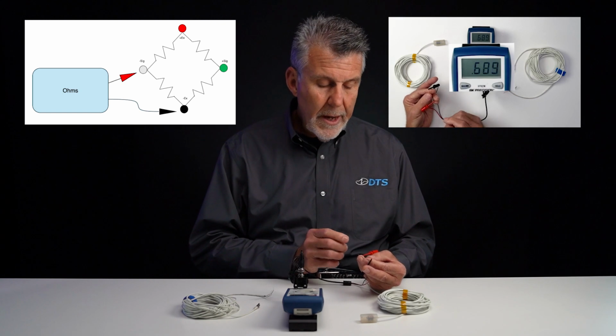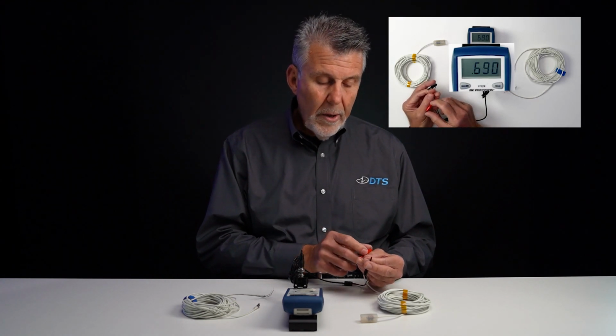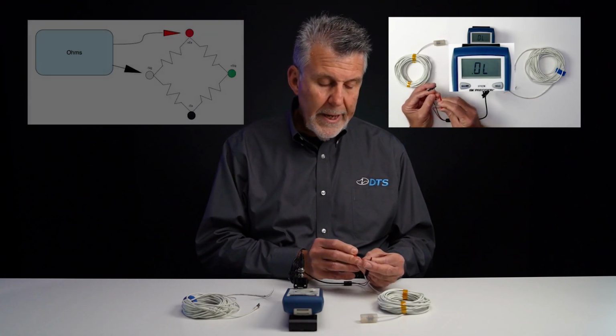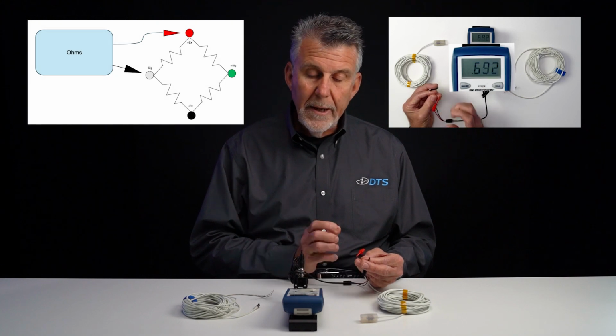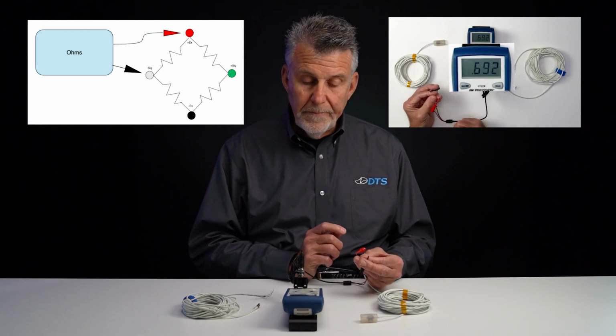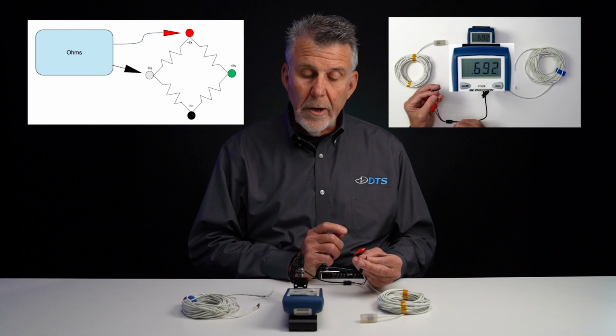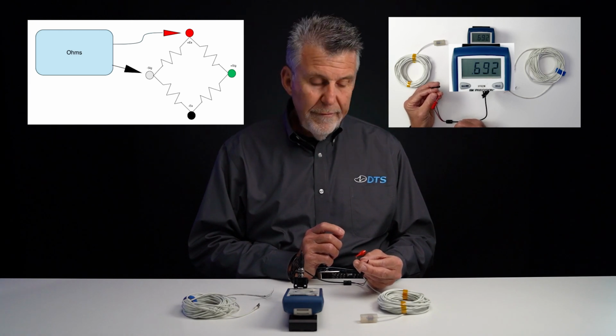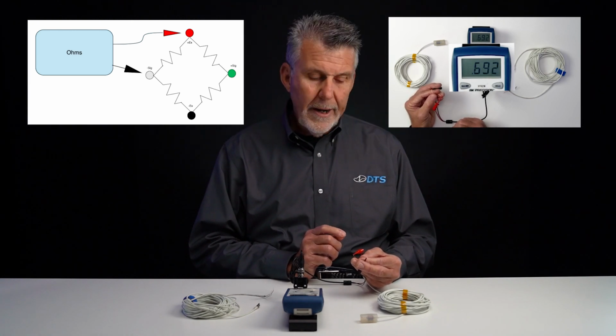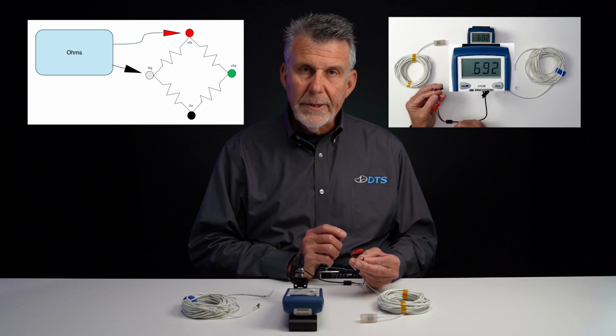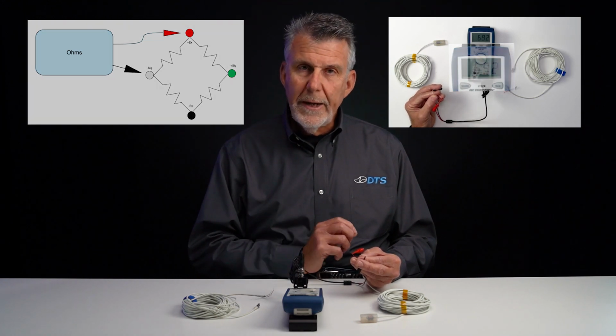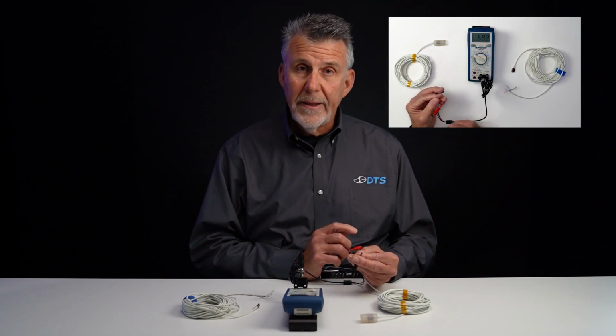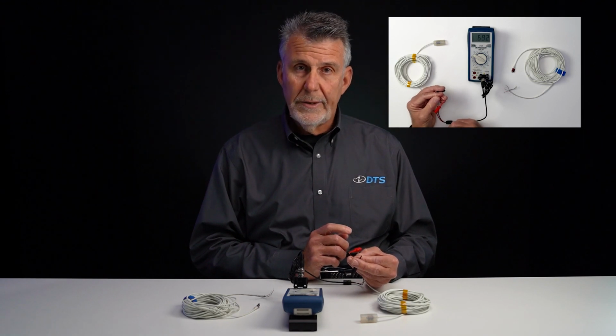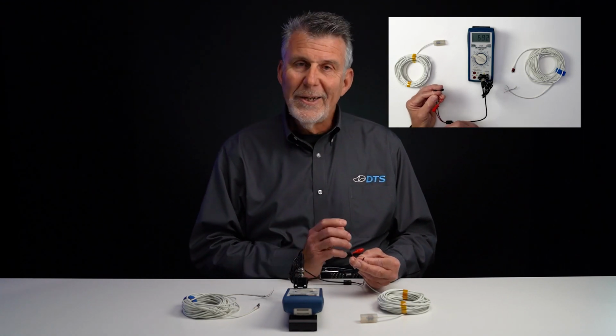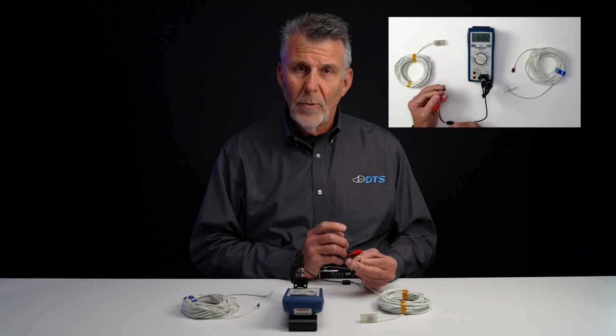I see 690 ohms. Okay, now I'm going to move over to the plus excitation, so I'm looking at the other half of the bridge, and I see 692 ohms, which is very close to the reading I got when I went to the minus excitation. This tells me that the minus signal side of the bridge is also balanced, and it actually is consistent with the fact that this sensor worked the last time I used it.